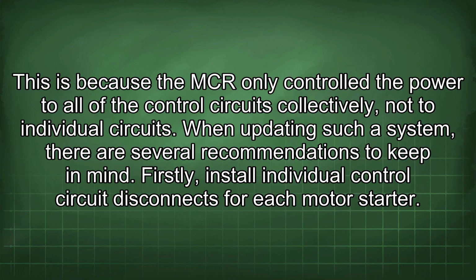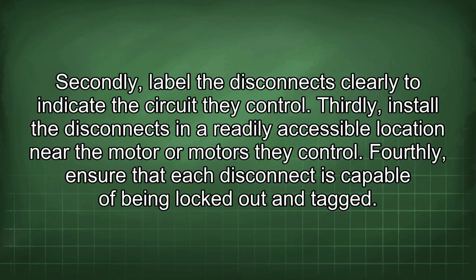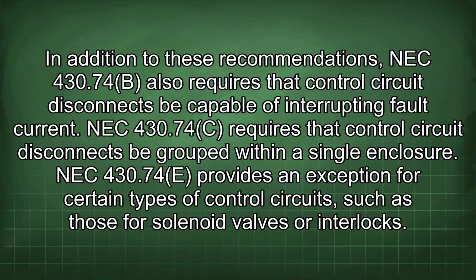Firstly, install individual control circuit disconnects for each motor starter. Secondly, label the disconnects clearly to indicate the circuit they control. Thirdly, install the disconnects in a readily accessible location near the motor or motors they control. Fourthly, ensure that each disconnect is capable of being locked out and tagged. In addition to these recommendations, NEC 430.74 B also requires that control circuit disconnects be capable of interrupting fault current.